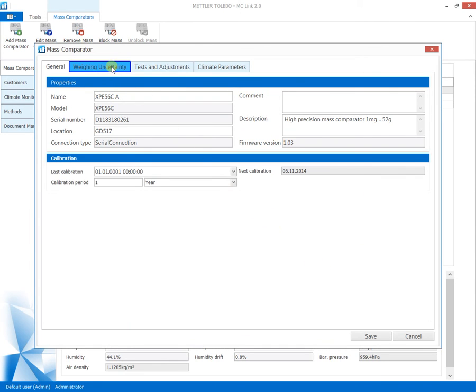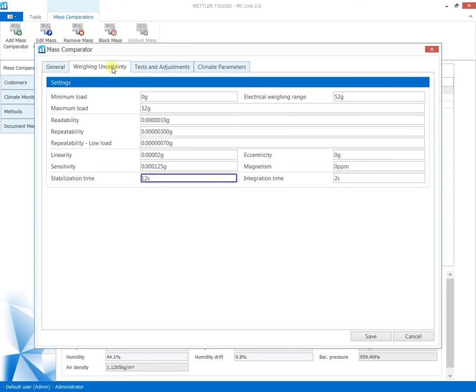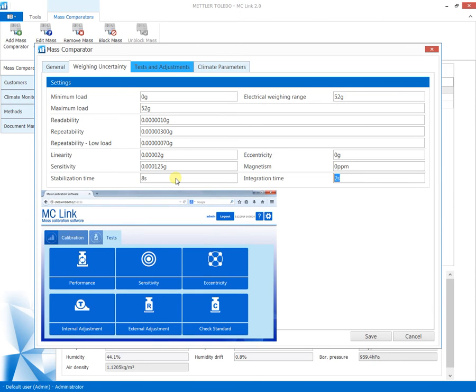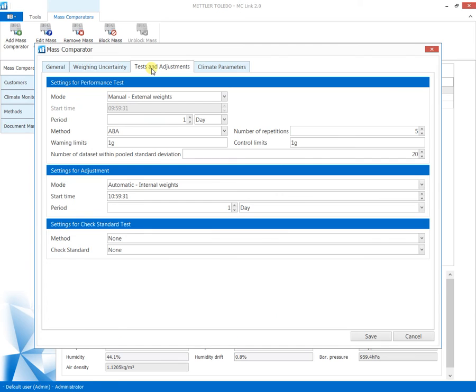In case you need to amend some technical specifications, which will be used for the uncertainty calculations, these parameters are found in the following sections. Adapt any parameter according to your local requirements. The parameters repeatability at nominal load and low load, sensitivity and eccentricity can be measured with the integrated comparator testing capabilities for determination of actual uncertainties.